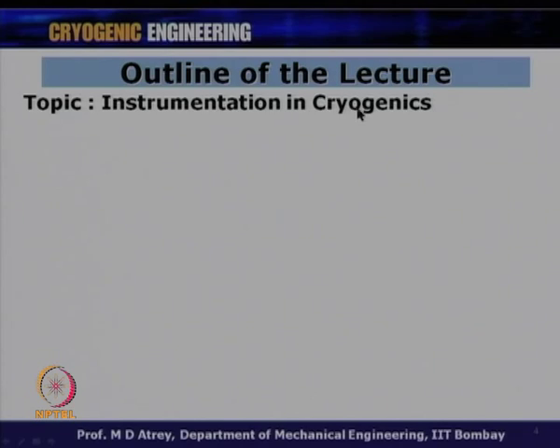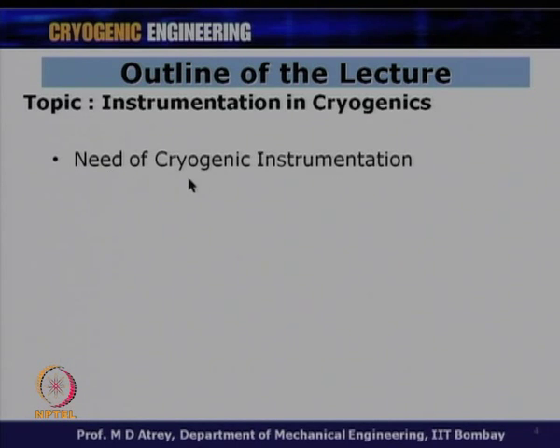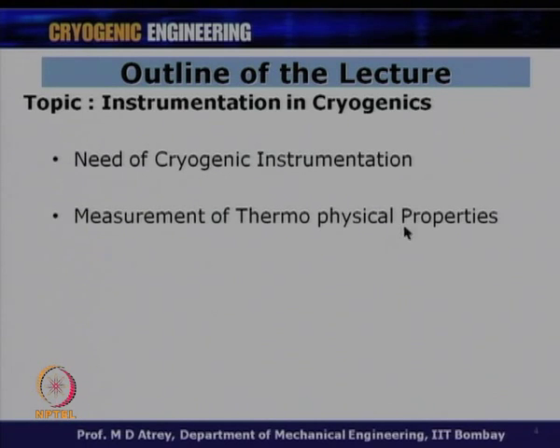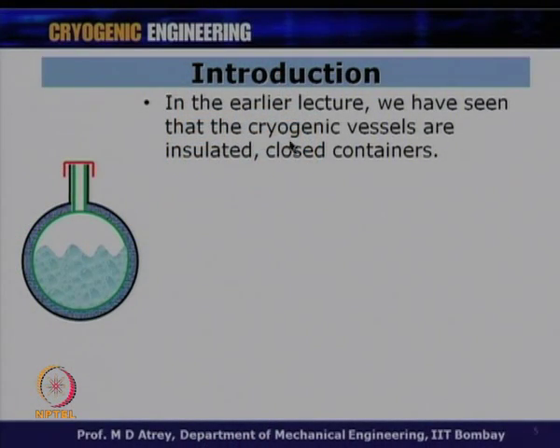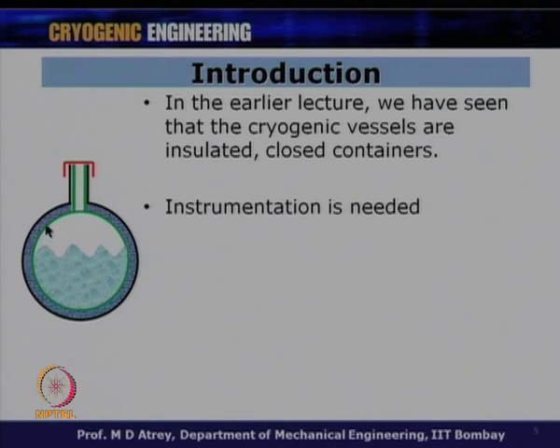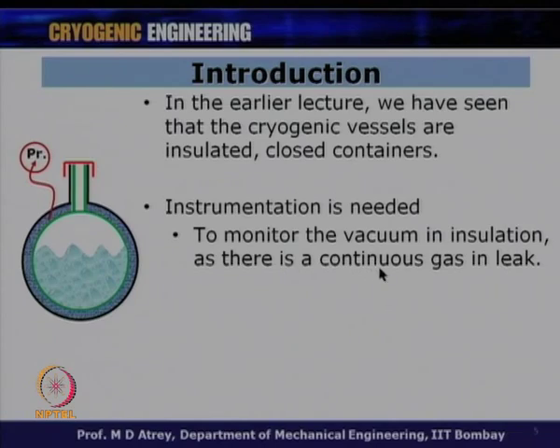The topic is instrumentation in cryogenics. Cryogenic vessels are insulated, closed containers. In order to monitor experiments in these containers—which hold a cryogen surrounded by insulation or vacuum—instrumentation is required. It is needed to monitor the vacuum in the insulation, since there is a continuous gas leak. The vacuum between the inner and outer vessel must be monitored because the boil-off of the cryogen depends on this vacuum.